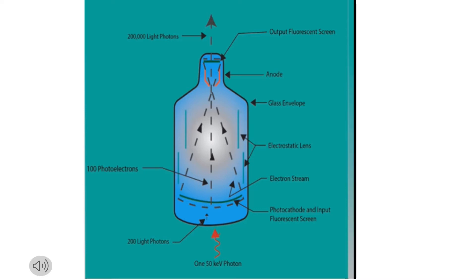Behind that you can see there's this photocathode which picks up the light and turns it into electrons, which are then accelerated towards the anode. It's similar to an x-ray tube, but instead of striking the anode, they strike the output phosphor.